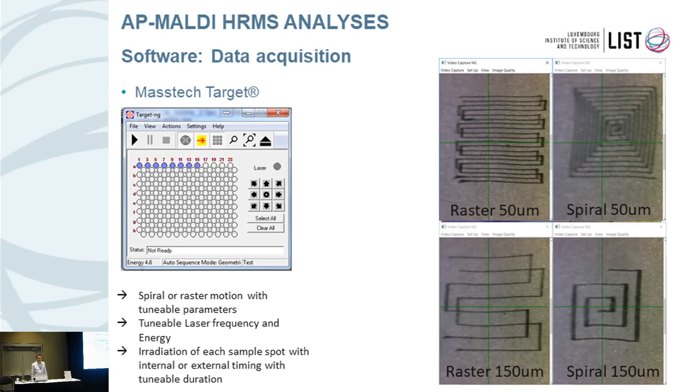There are two modes of operation. The classical approach is multi-spot analysis. We have the Target software which allows you to control the source, and we use typically SCIEX plates with 192 spots. You can select the spots of interest, and within each spot you can program the motion of the sample holder so you don't always irradiate the same position — using a raster motion or a spiral motion. You can tune parameters such as velocity of the spiral, distance between lines, laser frequency, and laser energy. The laser beam size is quite small — here the distance between lines is only 50 microns, meaning the spot size is in the range of 10 microns.